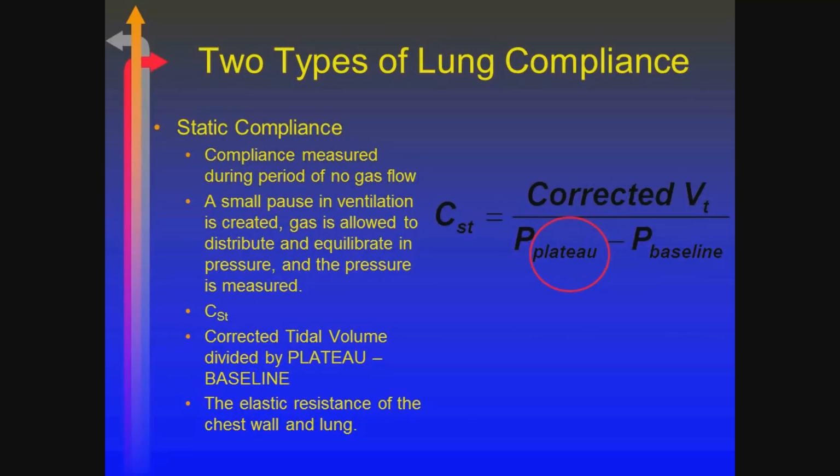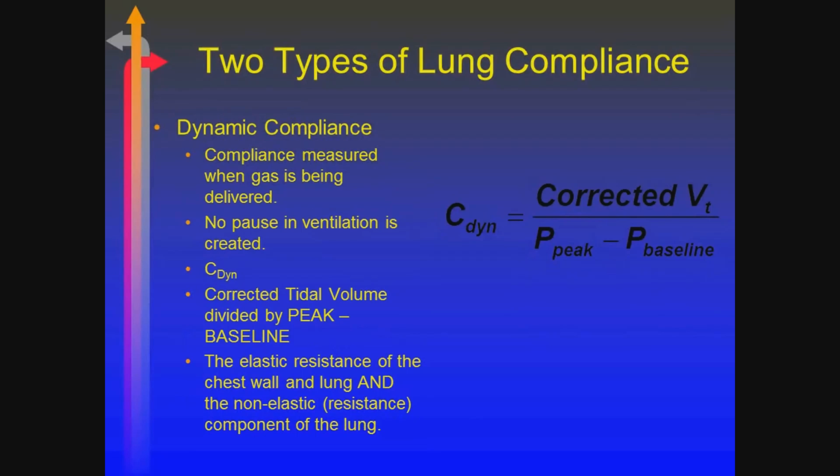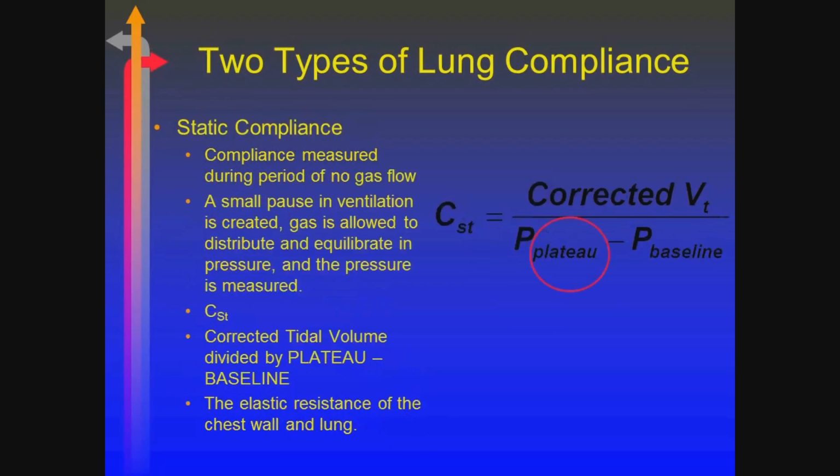So that's static compliance, okay? The other type of compliance that exists is known as dynamic compliance. And this is, back up a second here. This key part here: when you measure static compliance, the way that we create this plateau pressure is we have a small pause that is created at the end of the inspiratory phase.